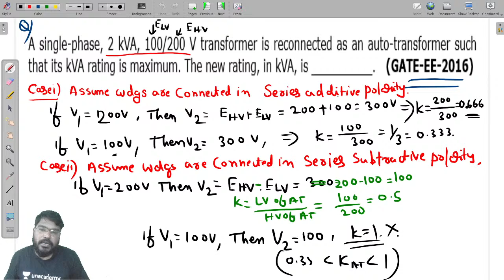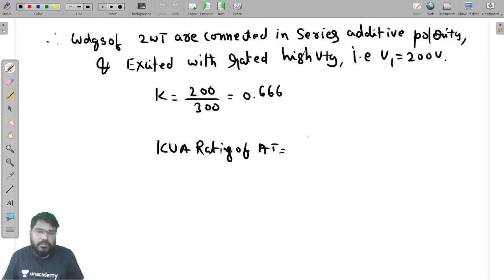Now calculate this part. 6 kVA, right? That's correct. So the kVA rating of the auto transformer is equal to 1 by (1 minus K) times the kVA rating of the two-winding transformer, which is 1 by (1 minus 0.66) into 2 kVA, equal to 6 kVA. So this is the answer for this question.